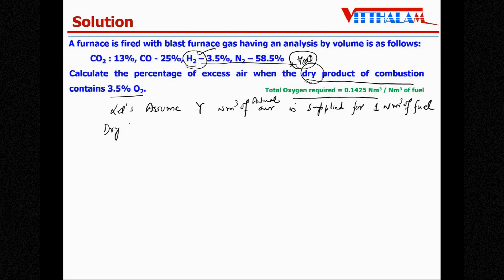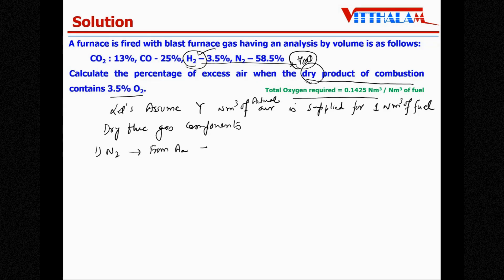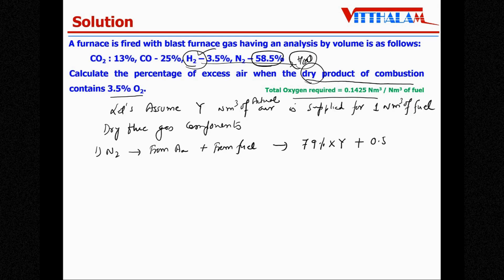Let's find out the dry flue gas components per nm³ of fuel. First is nitrogen. Nitrogen comes along with the actual air plus from the fuel itself. Nitrogen with actual air is 79% of y. Plus from the fuel, 58.5% is already there, so 0.585 nm³. So nitrogen in dry flue gas = 0.79y + 0.585 nm³ per nm³ of fuel.